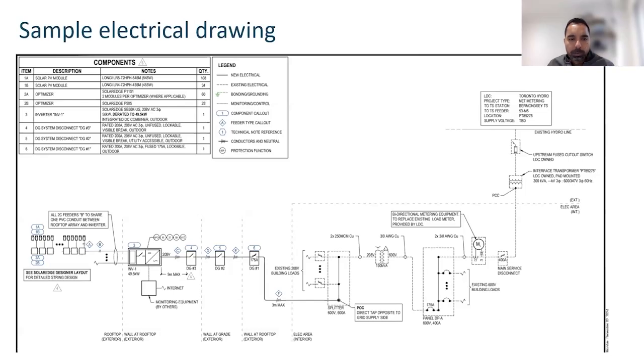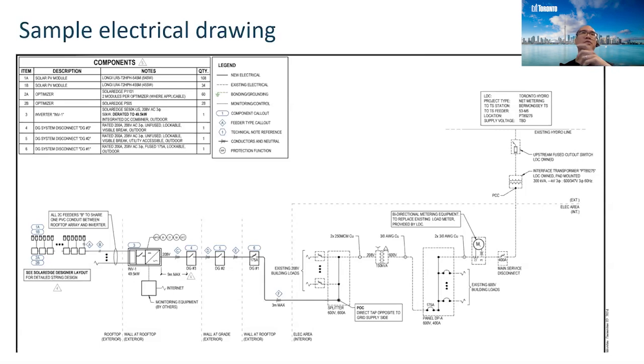So you were able to feed back using the inverter - the system we have is actually a 208 system, so we can connect to that splitter as shown on screen. One of the problems we have in Canada generally is the voltage for the inverter, because a lot of the equipment is designed for the States at 480, while we're at 600, at least in Ontario. So we always have to have a transformer somewhere in the design.